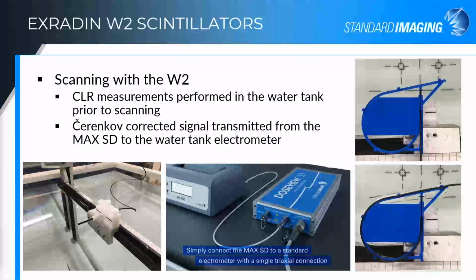I mean you're not applying bias to it, but when the beam is turned on, a signal is received by your electrometer. The advantage of this really is you can scan to find the center of the field. You can collect profiles, you can collect PDDs. If your system will let you do, well, you could drive it to depth and get point doses via the MaxSD itself, which would be the most accurate way to do it, rather than adding in the additional electronic noise from your scanning tank electrometer if you're doing point dose measurements that way. But it's really a wonderful tool for scanning small fields.